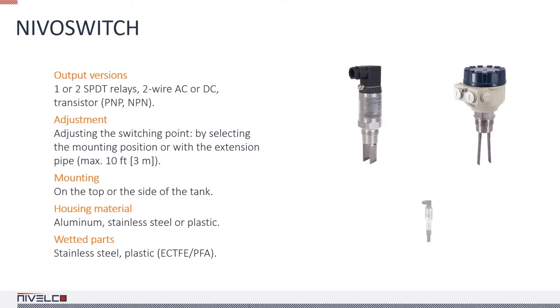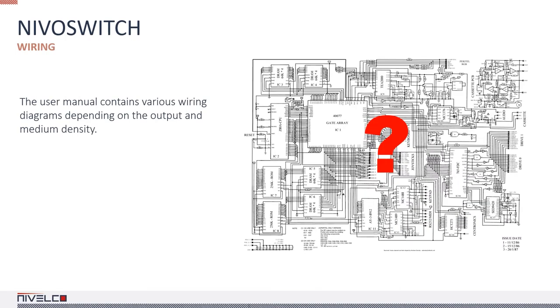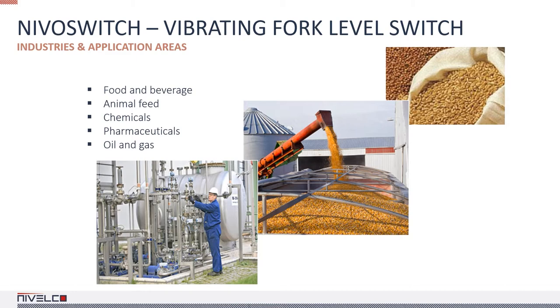The PNP-NPN transistor output versions can be connected directly to a PLC or a relay. NIVOSWITCH vibrating forks combined with UNICON PPK switching amplifiers can be used with high current loads. The UNICON PPK 312-8EX intrinsically safe switch unit is designed for EX vibrating forks. The user manual contains various wiring diagrams for different outputs and medium densities.